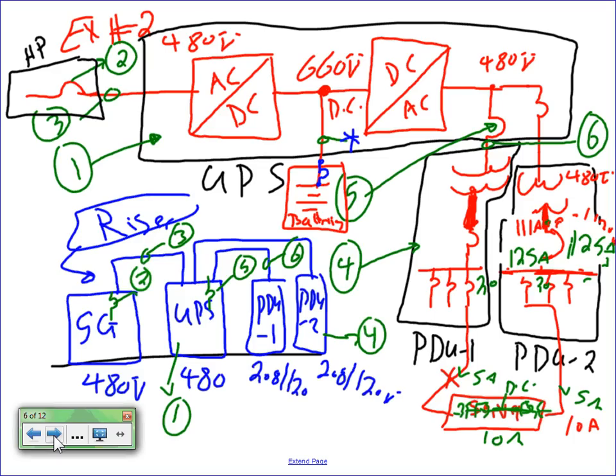Chris, I have to make you guys a cut sheet about PDU. When you get the 40 kVA PDU, it will give you a size of a panel. Say it's a 100 amp panel that's going to be tied to it, and how many circuit breakers you want in this PDU. So when you pick the PDU, it will give you the standard size panel that goes with it. That's why we didn't mess with what's inside here, and these all will be 20 amps guaranteed.